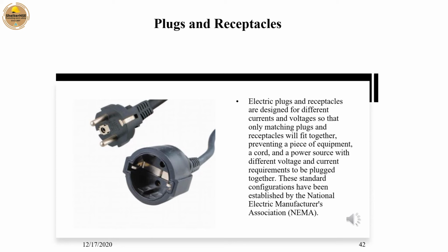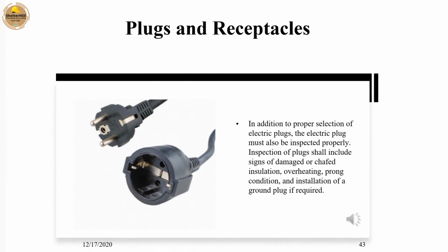These standard configurations have been established by the National Electric Manufacturers Association, NEMA. In addition to the proper selection of electric plugs, the electric plug must also be inspected properly. Inspection of plugs shall include signs of damaged or chafed insulation, overheating, prong condition, and installation of a ground plug if required.